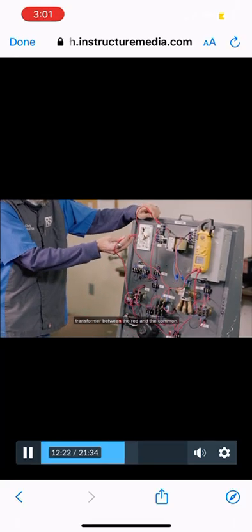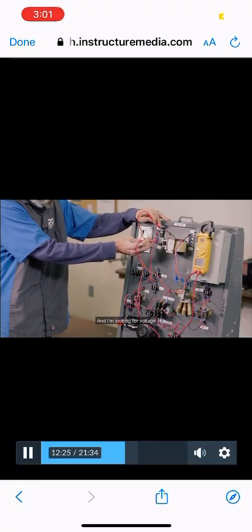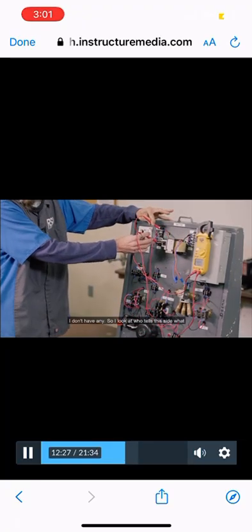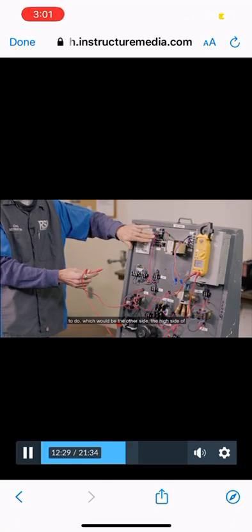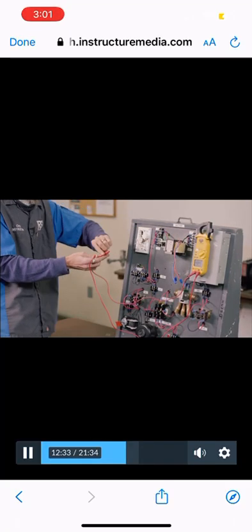So I'm going to go to the low side of my transformer between the red and the common, and I'm looking for voltage. I don't have any, so I look at who tells this side what to do, which would be the other side, the high side of that transformer. It takes the high voltage, transforms it down to a low voltage signal. So I'm going to go between L1 and L2, and I don't have any power there. So the last step that I would be doing is going to the disconnect.